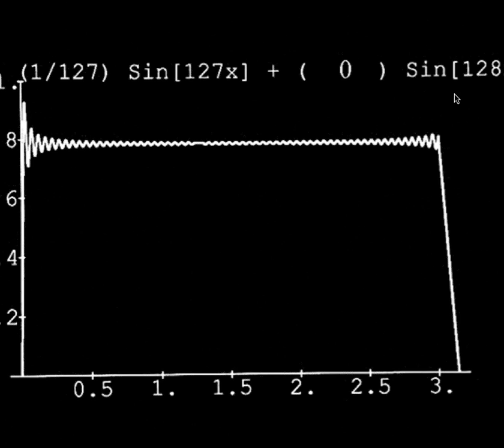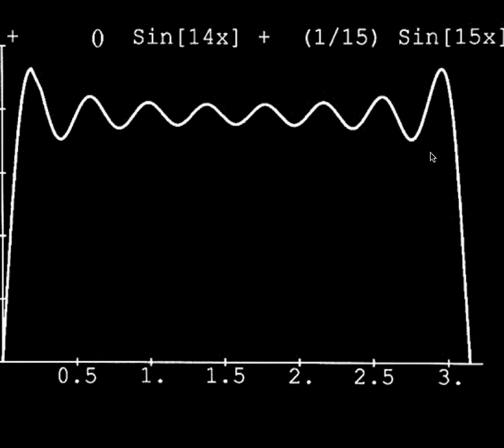That would mean it would take an infinite time to scan someone, which isn't acceptable. So if we stop at 128 or 256 phase encodings, rather than going to infinity, that's called truncation of the sequence, and that will give artifacts. Here, they're small artifacts if we do a lot of phase encodings. If we do fewer phase encodings, we get much bigger artifacts. But that's a truncation artifact.